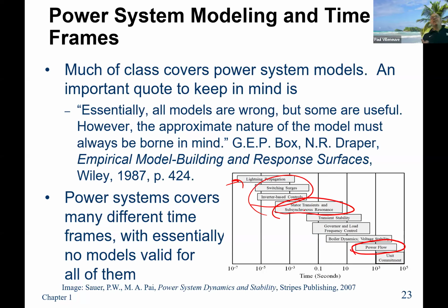That includes limiting fault currents. There are current limiting fuses that, if a fault occurs wanting to pull 400,000 amps, will knock that down to something like 50,000 amps, so way less damage happens. Does anybody know how that works, how you knock down current with a current limiting fuse?